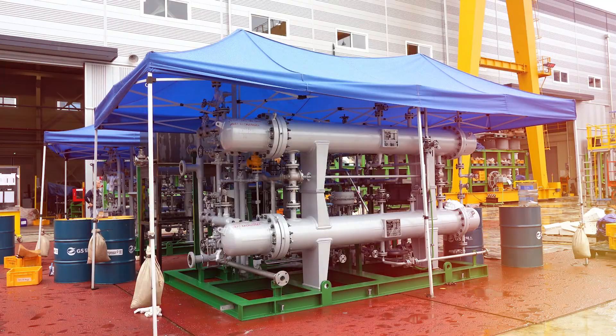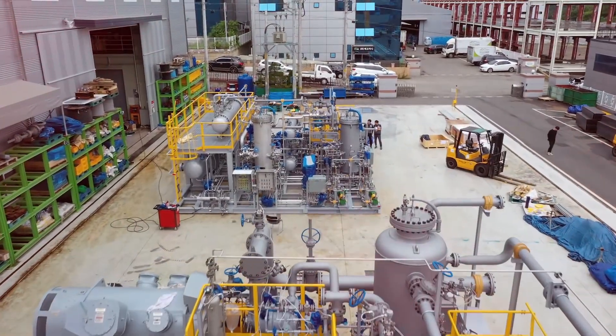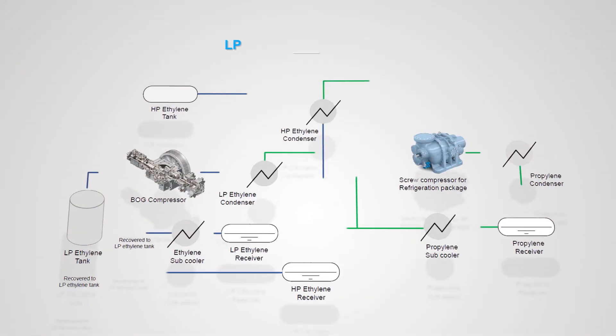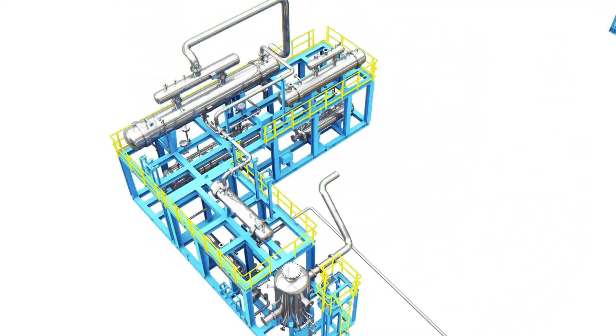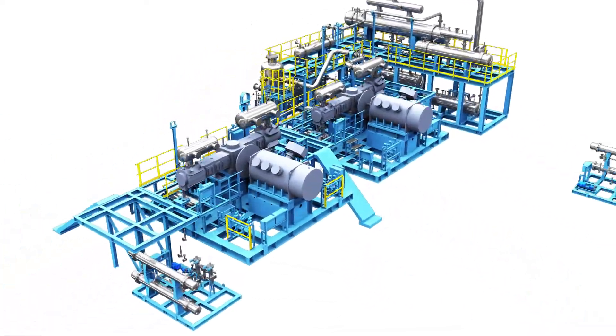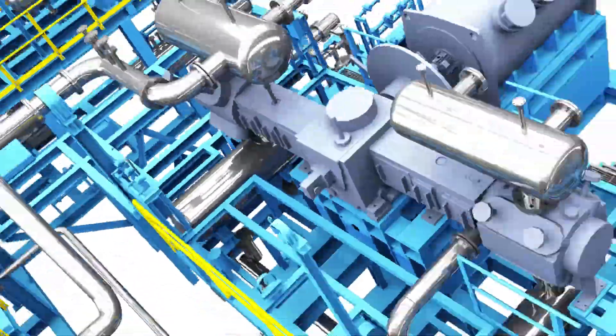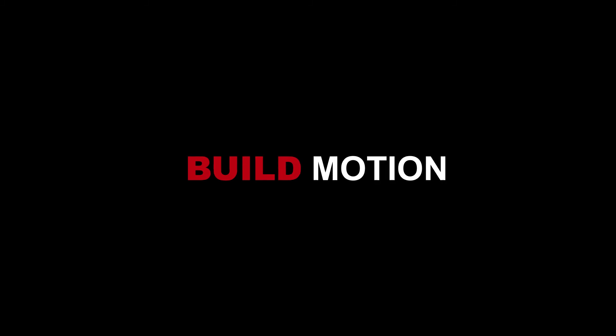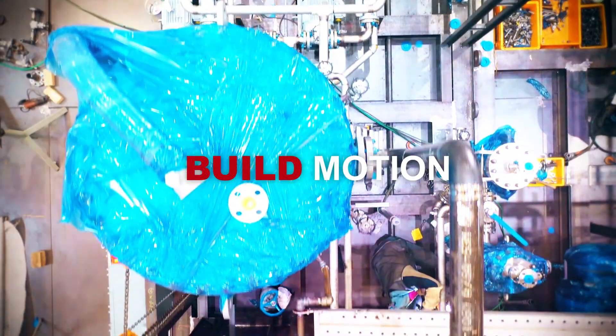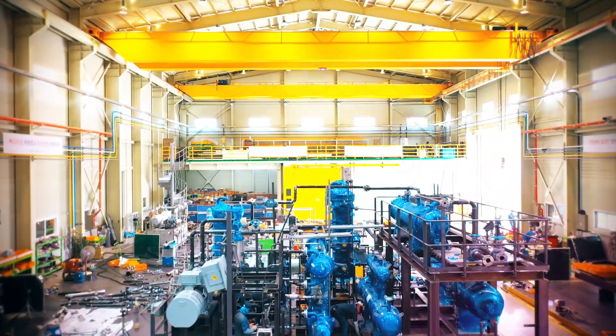Therefore, one of our key technologies is the BOG compressor system package, which recovers BOG back into the storage tank by boosting it to the most efficient pressure level through compression and then re-liquifying the gas through a heat exchange with the refrigerant supplied from the refrigeration system. The ethylene BOG liquefaction package consists of a cascade refrigeration system with an ethylene reciprocating compressor and a propylene screw. The video shown here is the fieldwork process of the BOG compressor system package that we have been manufacturing for a long time.